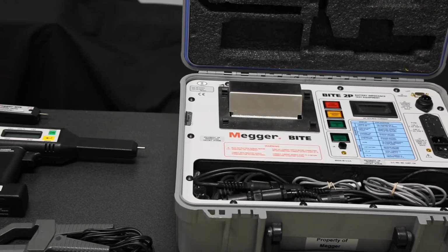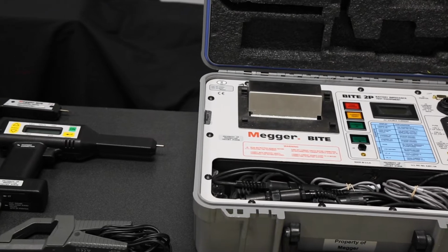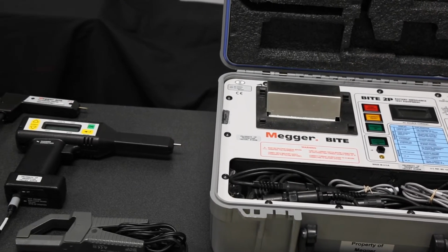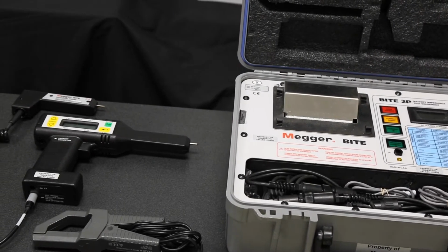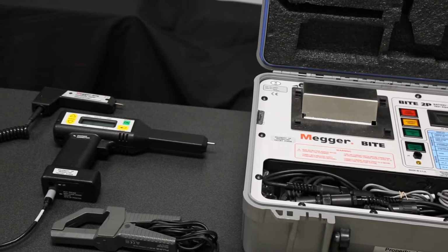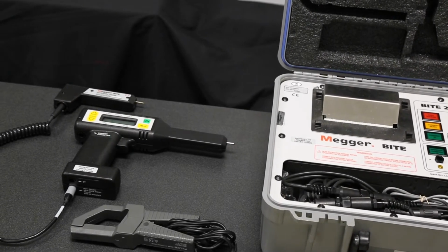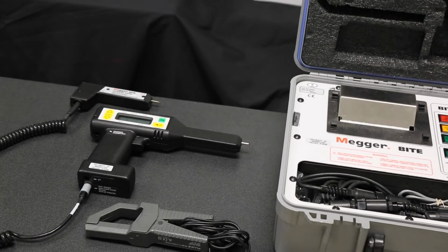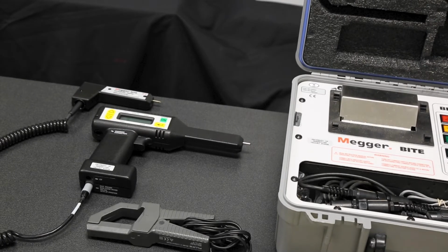The BITE2 is a two-part instrument. A transmitter is connected across the entire string. The transmitter will then inject 10 amps of test current through the entire string. A separate lightweight receiver pistol is then used to take both the battery and intercell or strap measurements.